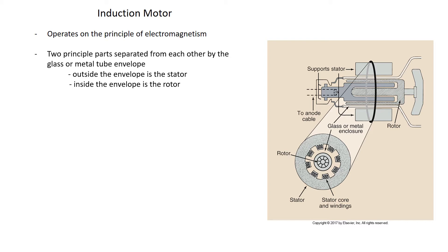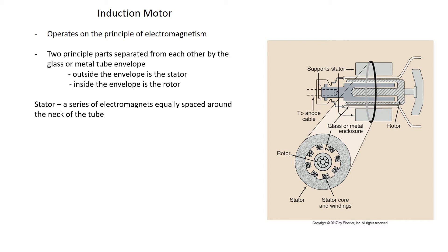There are two principal parts separated from each other by either glass or metal tube envelopes. The outside of the envelope has the stator, and the inside is the rotor. These two parts, the stator and rotor, do not physically touch one another. The stator is a series of electromagnets equally spaced around the neck of the tube. The rotor is a shaft made of bars of copper and soft iron.